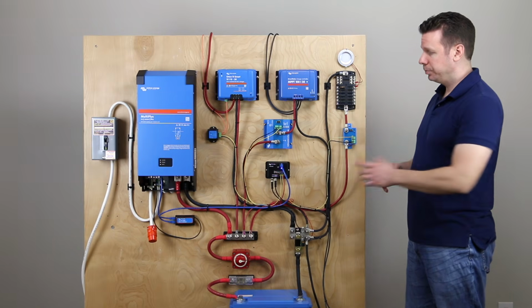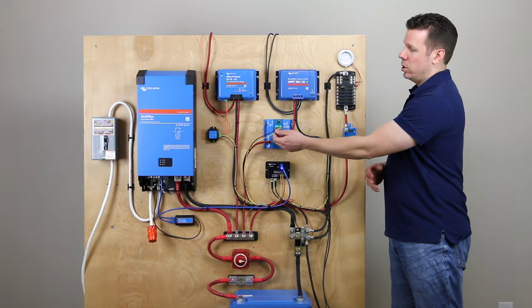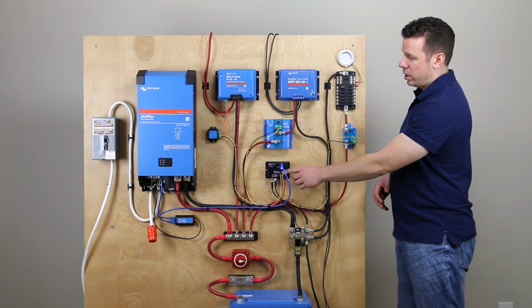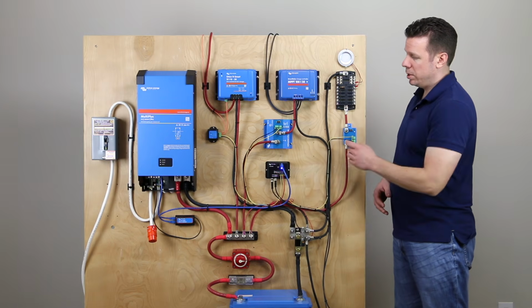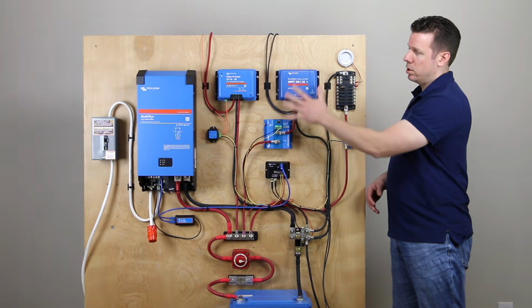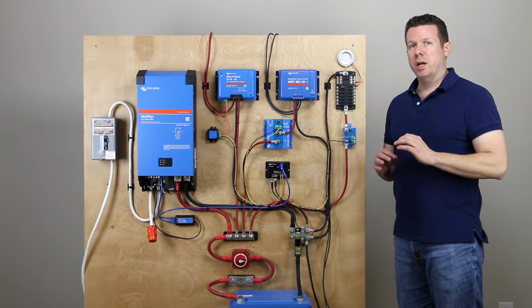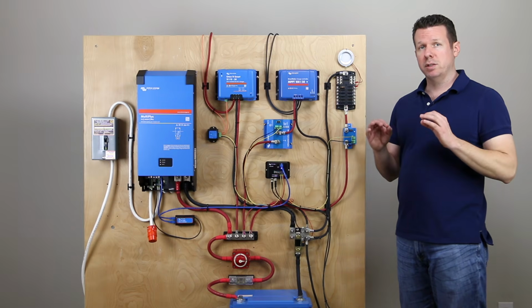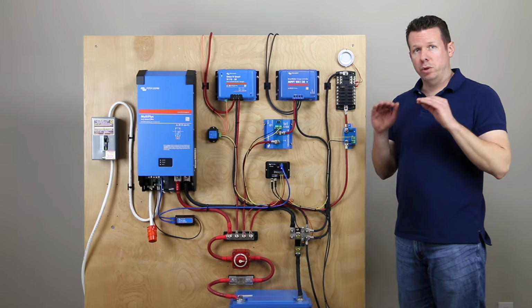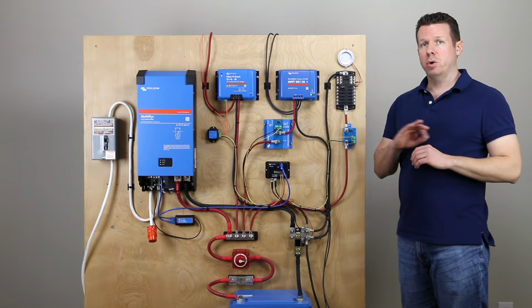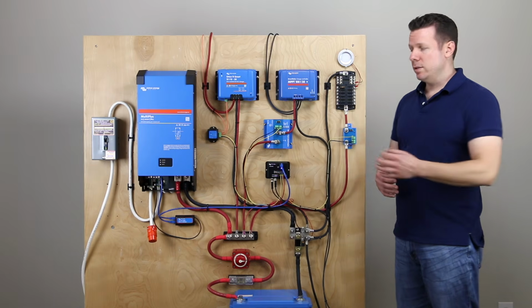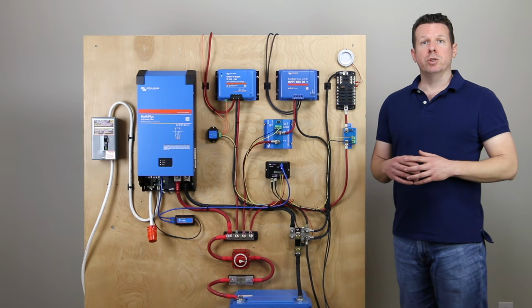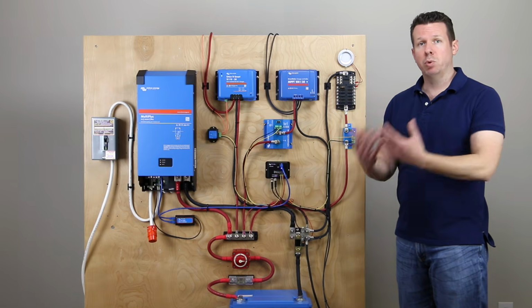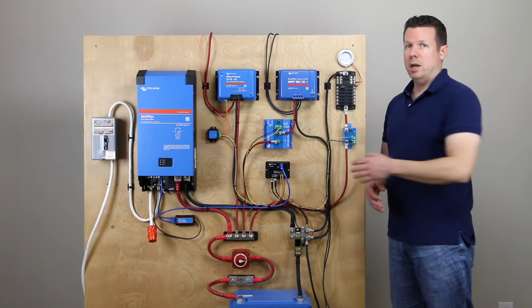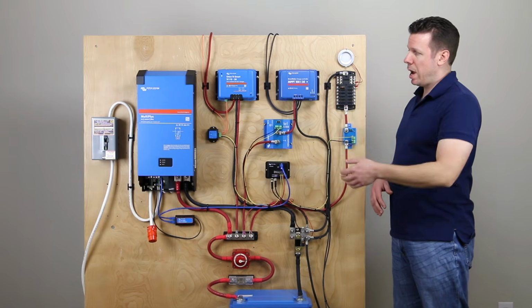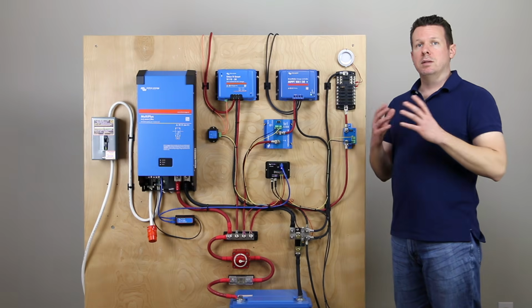In use case 1, these yellow wires go out to the BatteryProtect units, one for charge disconnect and one for load disconnect. The loads connect here, and the charger connects here to the solar charger. These BatteryProtects are set to lithium ion mode, which shuts down their normal low-voltage shutdown functionality and turns them into relays controlled by the BMS. Under normal circumstances, the BMS sends a 12 volt control voltage down this yellow wire telling them to turn on, letting the loads get power and the solar power come through to the battery.